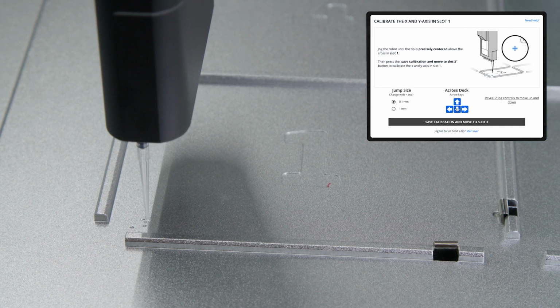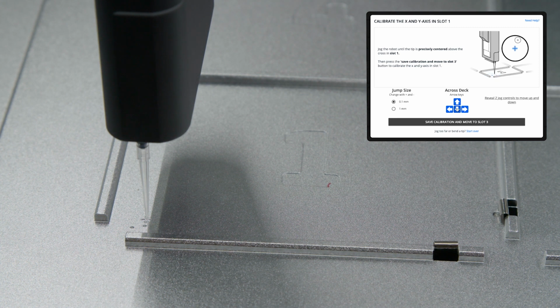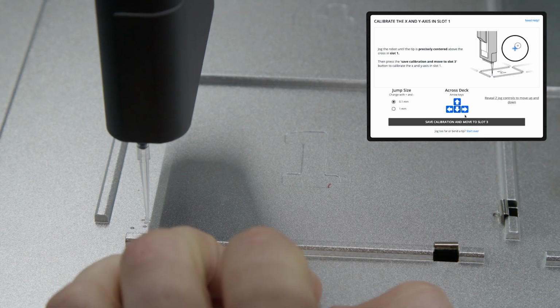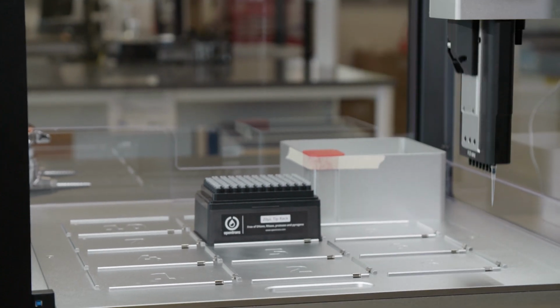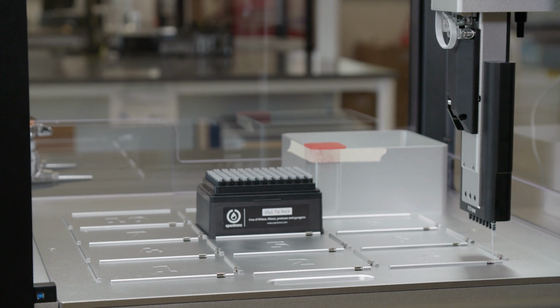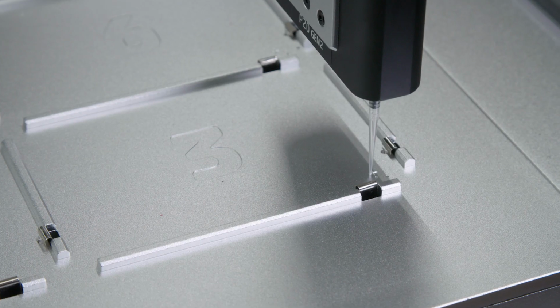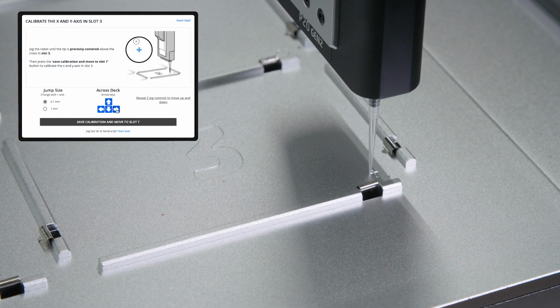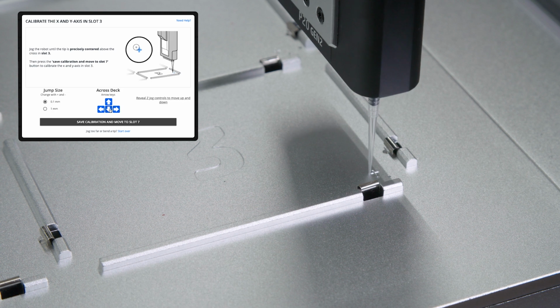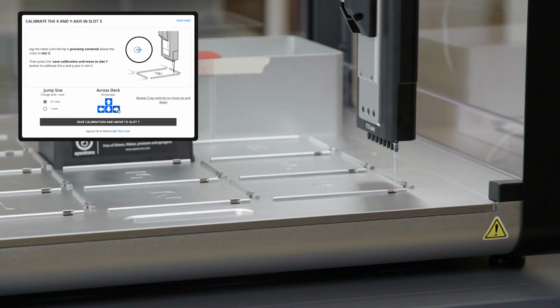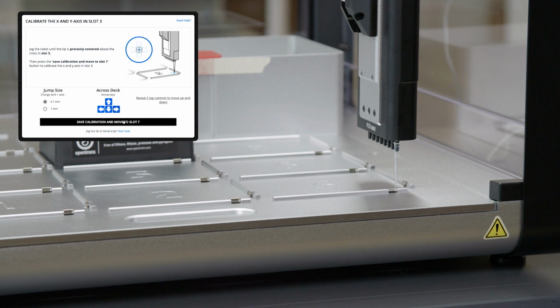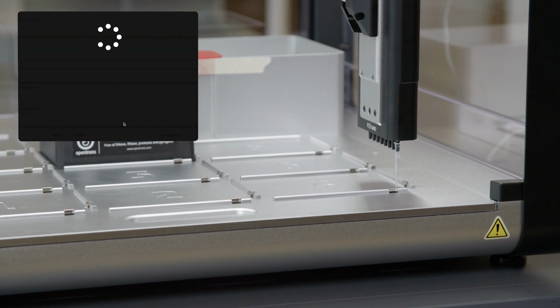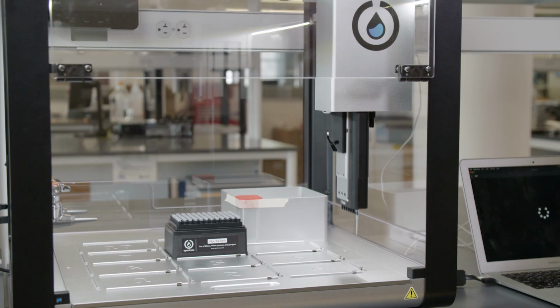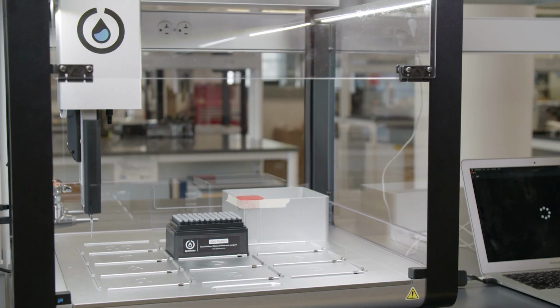The tip is precisely centered in the cross in slot 1. So I will save this calibration, and then the pipette will move to slot 3. As in the last step, I now need to make sure that the tip is centered in the cross in this slot. The tip is precisely centered in the cross in slot 3. So I will save this calibration, and the pipette will move to the cross in slot 7.